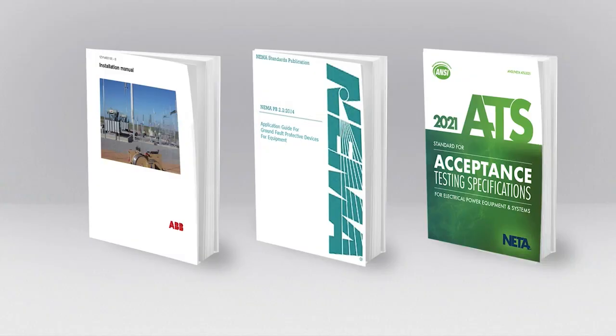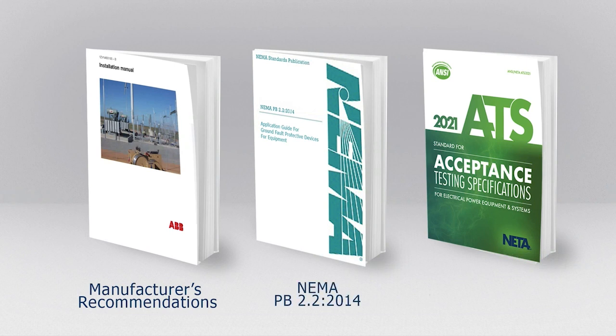So how are we going to make sure that we comply with the National Electric Code? Well, first we're going to use the manufacturer's instructions and recommendations. That's going to be first and foremost. They're going to give us that guidance. Second, we're going to refer to NEMA PB 2.2-2014, which is going to give us a lot of the construction elements and performance elements of that ground fault system. And third, and importantly, we're going to use the NETA testing standards to do the field verification and testing of that ground fault protection system in the field.